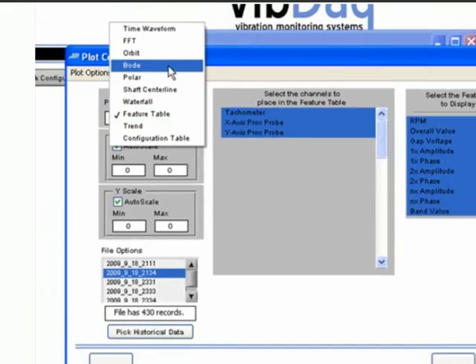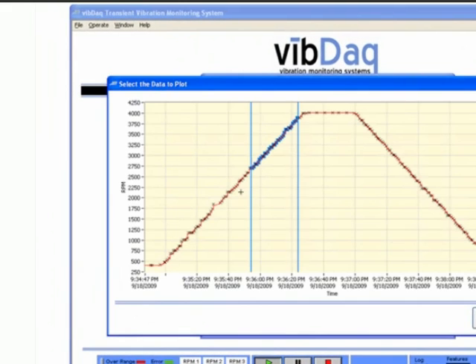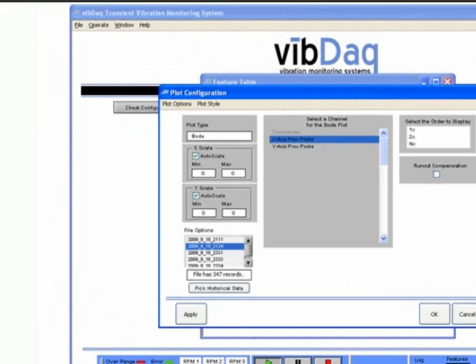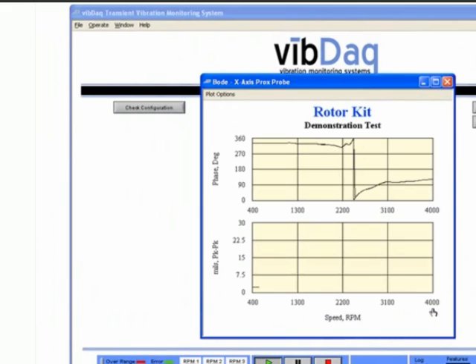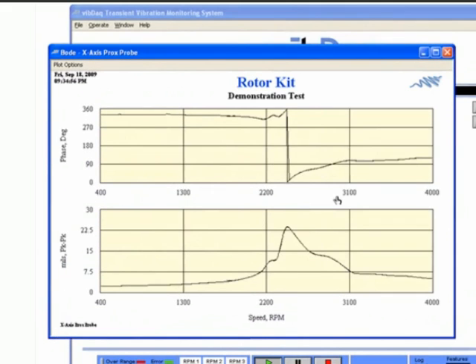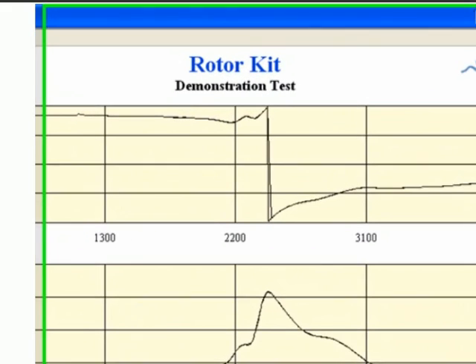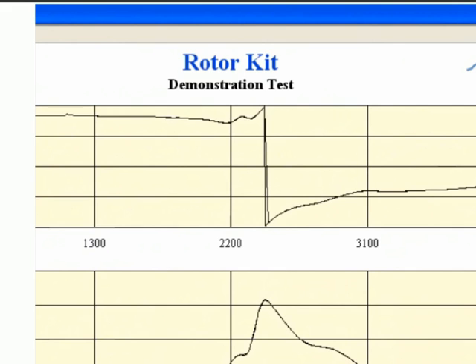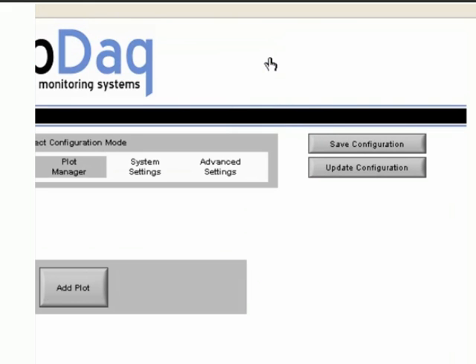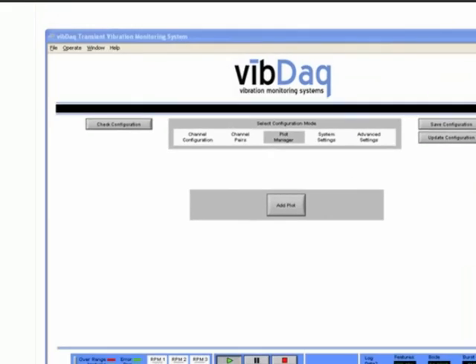The Bode plot allows you to see the magnitude and phase for a specific channel and order over a variety of speeds. The window contains two stacked plots with the same x-axis speed values. The lower plot shows magnitude on the y-axis, while the upper plot shows phase. Identifying which speeds cause increased vibrations and phase changes are critical to understanding the behavior of your system.